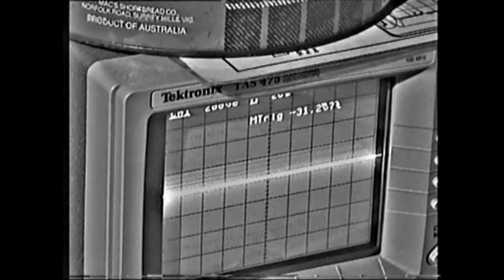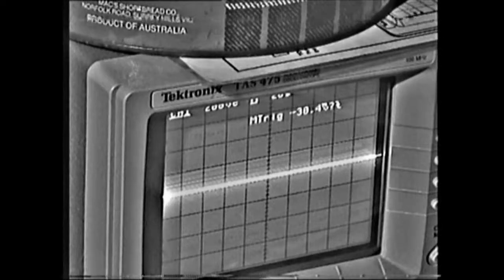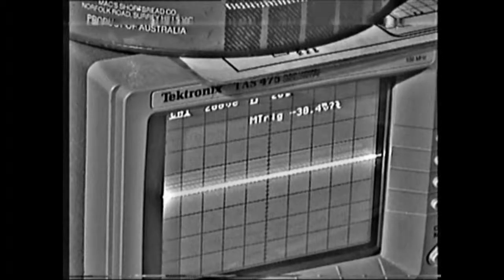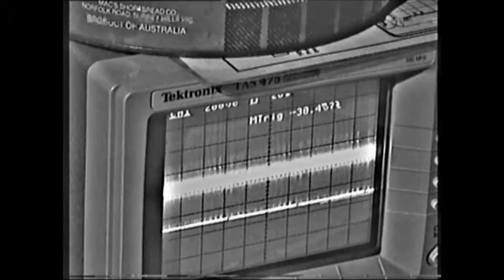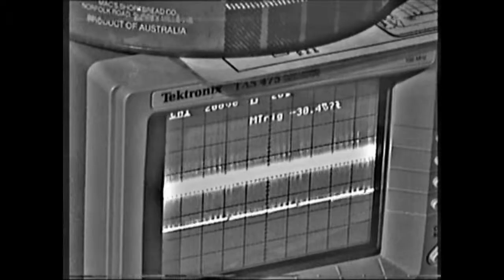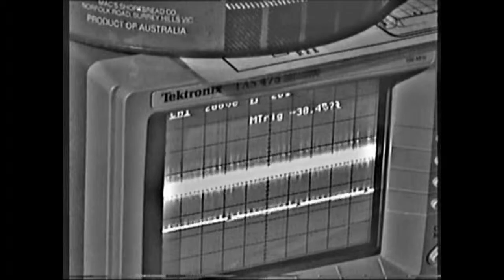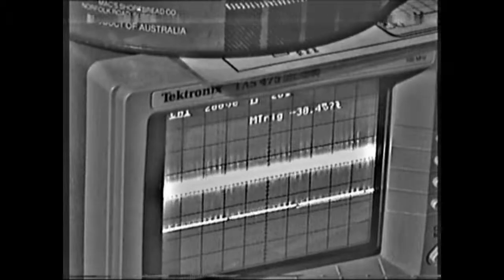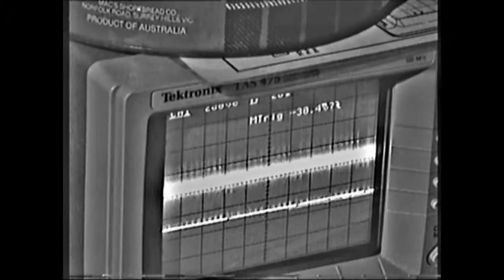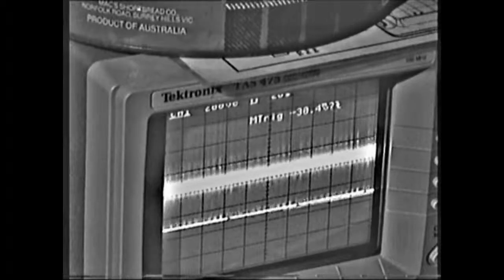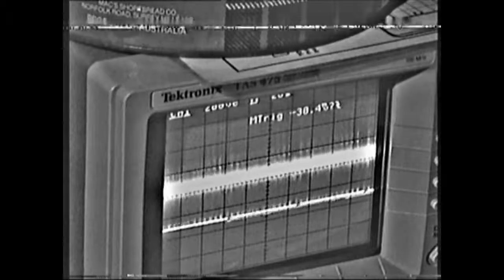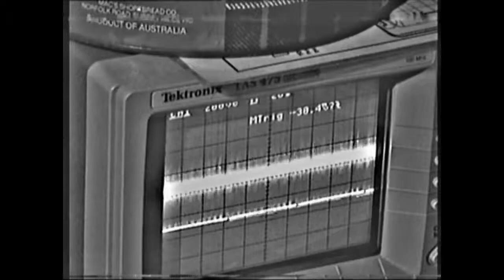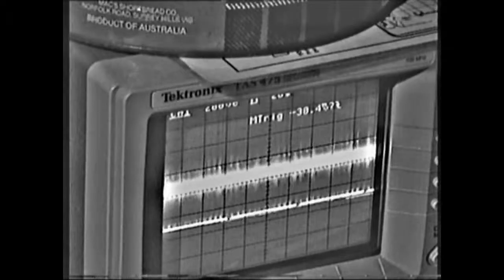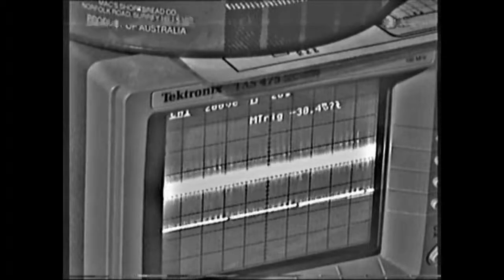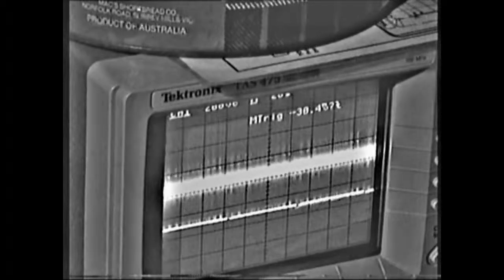So our problem, I believe, lies in the tube itself. Because if the preamp is amplifying noise, we get noise at the output, the head amp should by all means be working. But we're getting nothing coming from the target, so it means the tube is screwed, more than likely — unless the target lead is broken somewhere, which can also be a possibility.